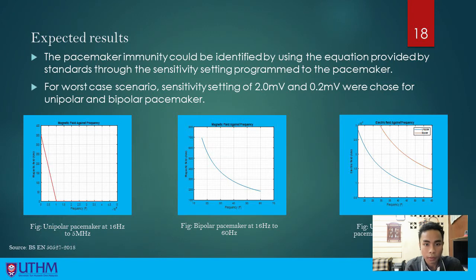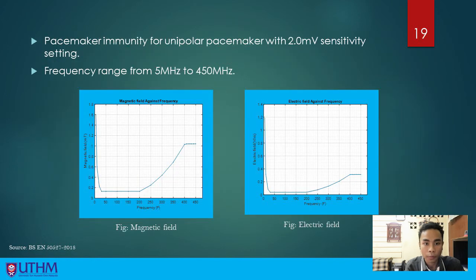The slide here shows the pacemaker immunity that has been calculated for unipolar and bipolar pacemakers at certain frequency levels, from low to high frequency. The frequency range from 5 MHz to 450 MHz will be done for unipolar since, according to some research, the bipolar pacemaker design is 10 times more immune to EMI than the unipolar pacemaker.